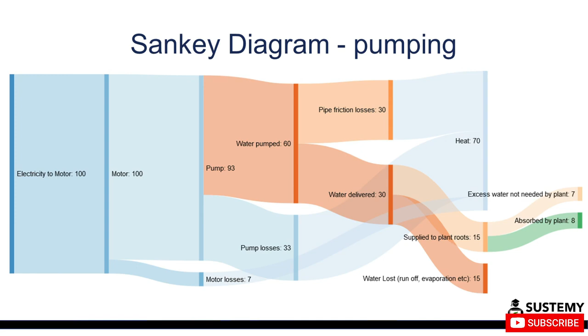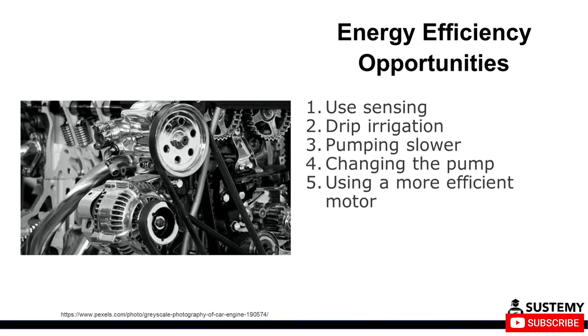So many engineers will look at a pump and their first thought will be a more efficient motor. But by preparing a Sankey diagram, you can see that there are opportunities that could give much larger savings. The overall system is only 7% efficient. Looking at this diagram, you can start to see that energy efficiency opportunities could include using sensing so as to not over-irrigate, using a drip irrigation system rather than a spray irrigation system to reduce water loss from runoff and evaporation, pumping slower to reduce the pipe friction losses, and changing to a more efficient pump. And then finally, looking at a more efficient motor. It should be possible to save both energy and water.